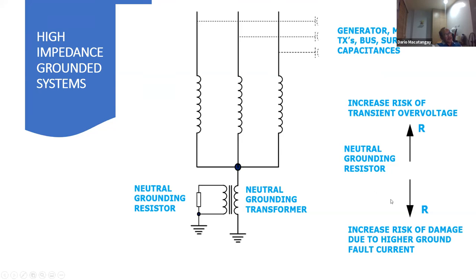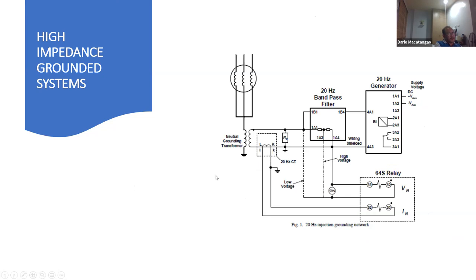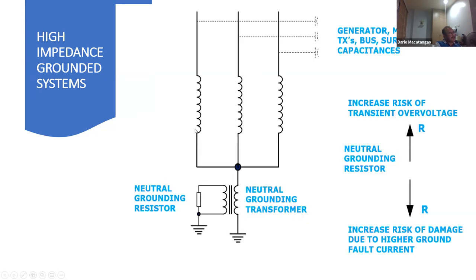However, if you decrease the resistor rating, it actually exposes the generator to higher damage due to higher ground fault current. It's because when you decrease the resistance, you're increasing the ground fault current. So that's typical, and this is typically used in the plant. In order to cover the additional 5% here, if you have a fault on the remaining 5%, this is actually destructive sometimes, because if you have a fault here and there's another fault on part of the winding, it can remain undetected. If it is not detected, then it could damage the generator.